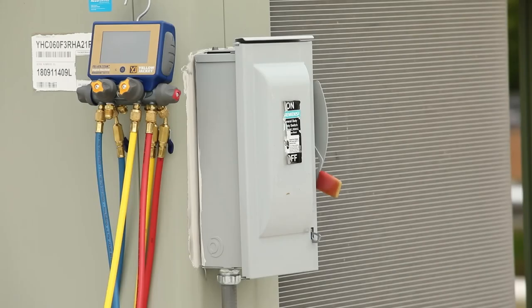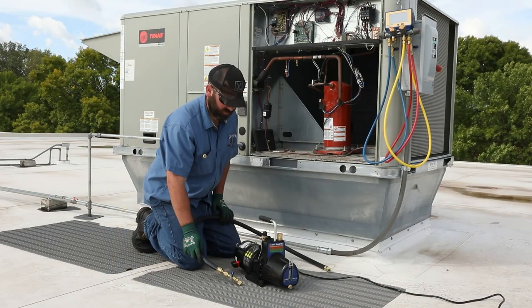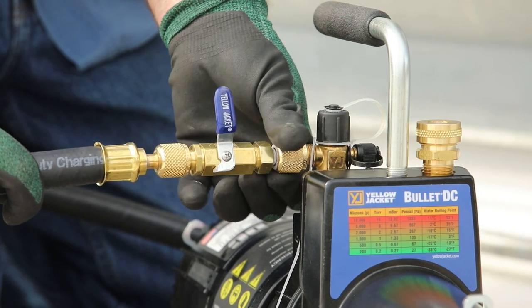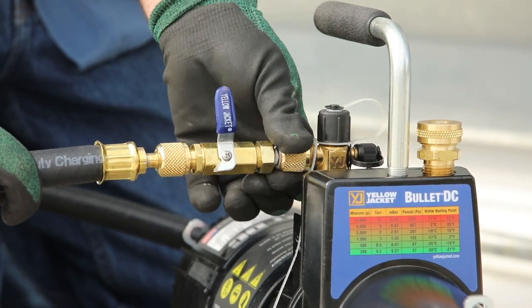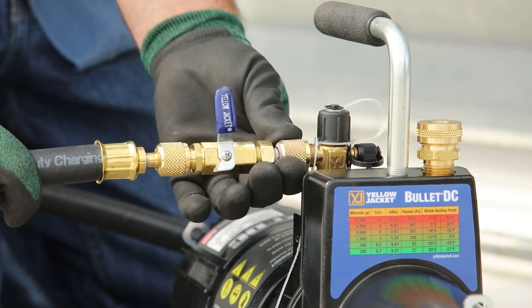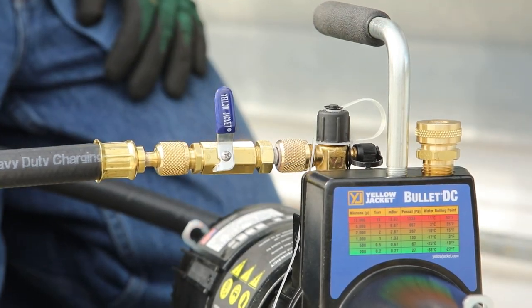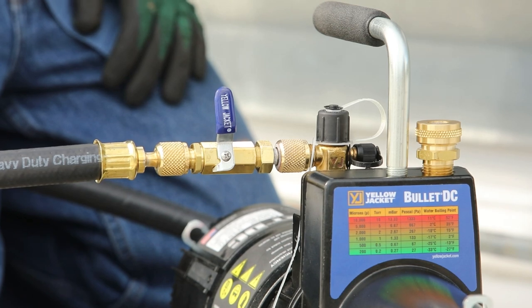Make sure the power to the unit is in the off position before starting any service. Attach the 3/8 inch end of a large diameter evacuation hose to the 3/8 inch intake fitting on the Bullet DC vacuum pump. The intake fitting supports 1/4, 3/8, and 1/2 inch hose connections for compatibility with a variety of system connections and hose configurations.